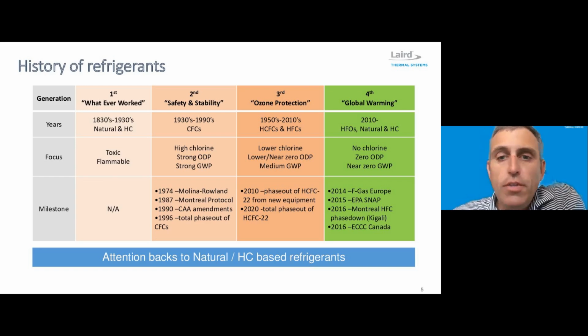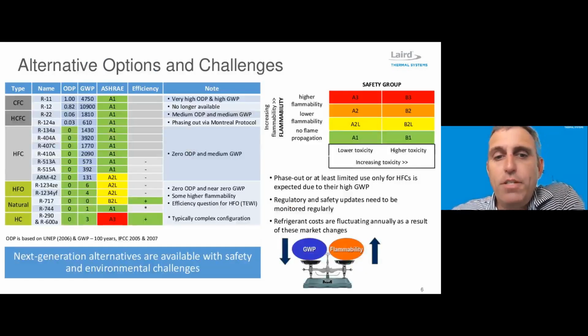So these you can see we've kind of come back to where we started nearly 200 years ago in using some of the natural and hydrocarbon refrigerants. And so these have no chlorine, so there's zero ozone depleting potential, and they also have very, very low, some have zero global warming potential. And so we can look a little bit more specifically at what some of these are. You can see on the upper right-hand side here, ASHRAE has put together a classification, if you will, for the types of refrigerants in terms of their flammability and toxicity.